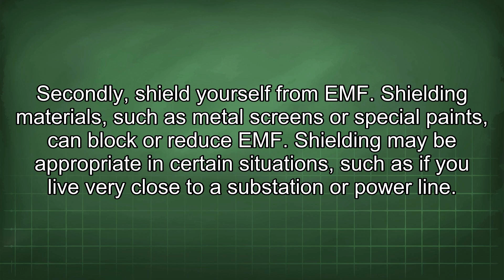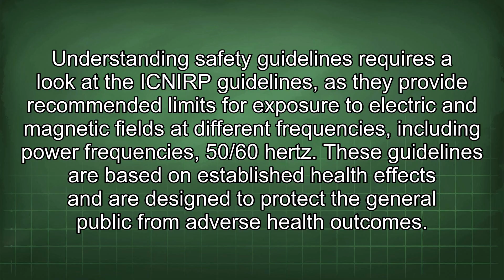Understanding safety guidelines requires a look at the ICNIRP guidelines, as they provide recommended limits for exposure to electric and magnetic fields at different frequencies, including power frequencies 50/60 Hz. These guidelines are based on established health effects and are designed to protect the general public from adverse health outcomes. The electric field reference levels for occupational exposure at 50/60 Hz are typically around 8.3 kV/meter, while for the general public, they are around 4.2 kV/meter.